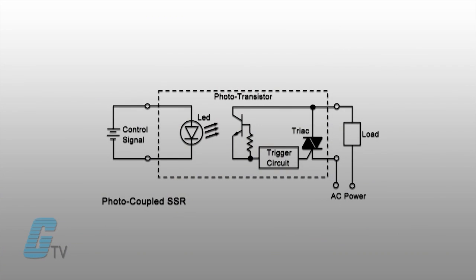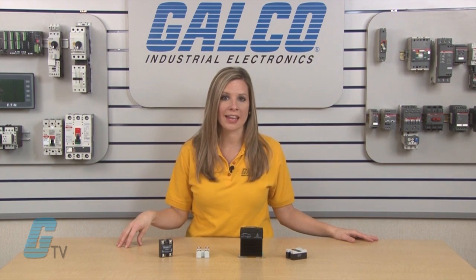A typical solid state relay has an optical semiconductor, such as photocouplers, that isolates the input signal by converting the electrical signal into an optical signal. A circuit is activated when a voltage higher than the relay's specified pickup voltage is applied, and is deactivated when the voltage is less than the minimum dropout voltage.